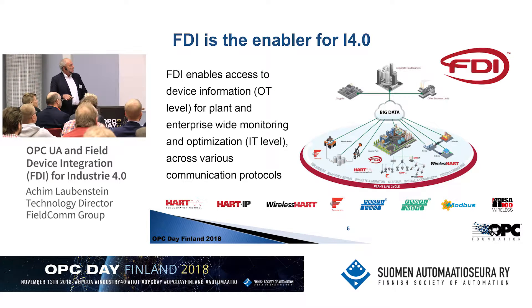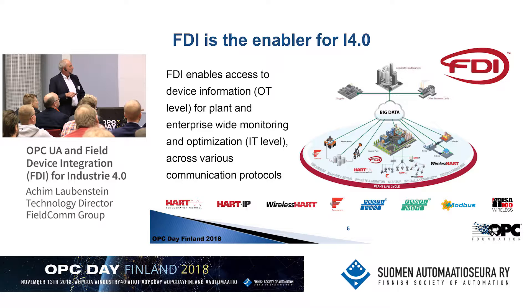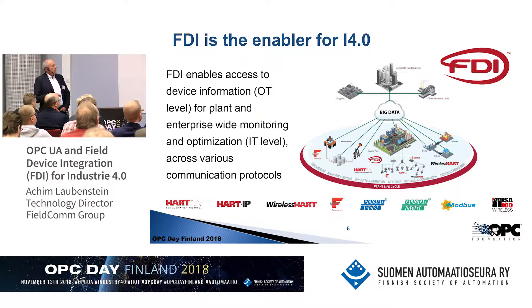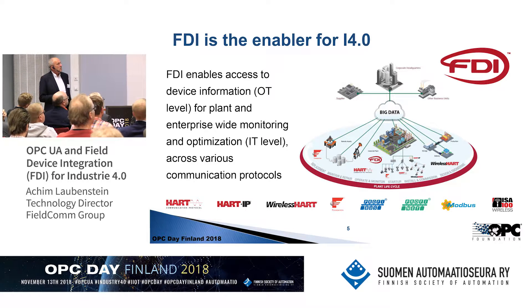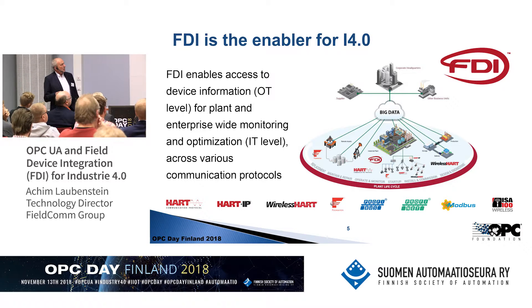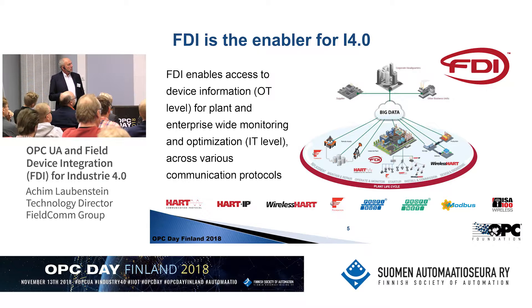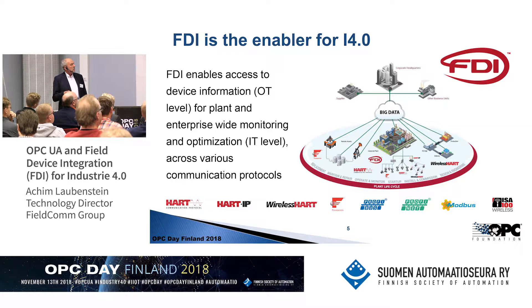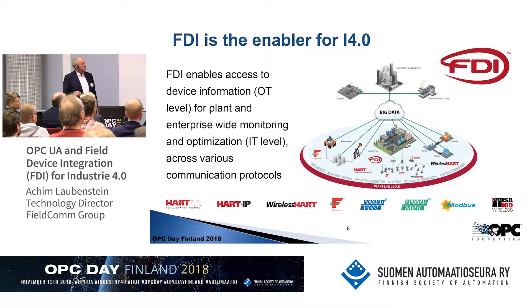FDI covers all those different kinds of communication protocols that are used in process automation — the different variants of HART FSK, HART IP, wireless HART, Foundation Fieldbus, Profibus, Profinet, Modbus, and also ISA 100, which is another wireless protocol. FDI on one hand helps to integrate those field devices into automation systems and allows to configure and maintain those field devices in a standardized way, but it also enables providing data from those devices to higher-level applications, from the various fieldbuses to the cloud.